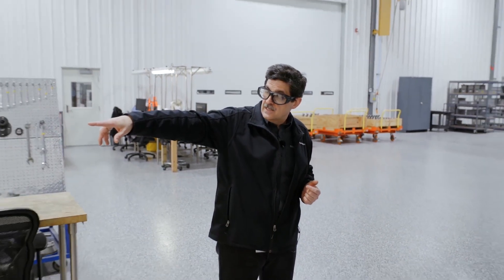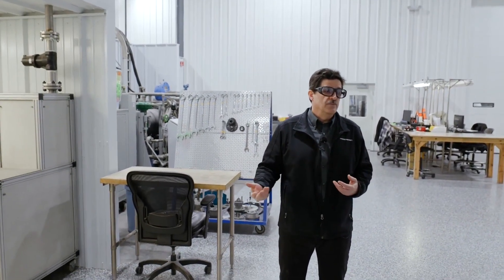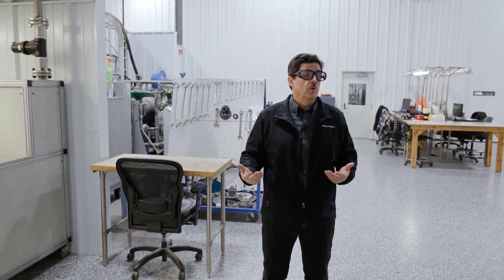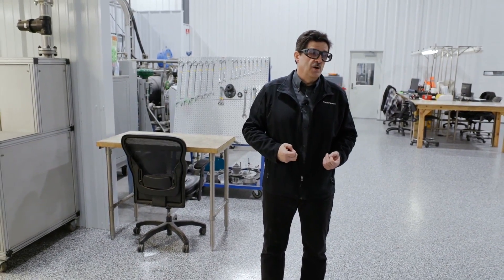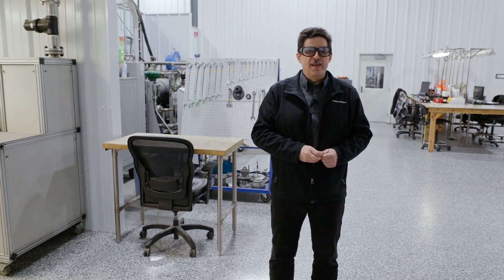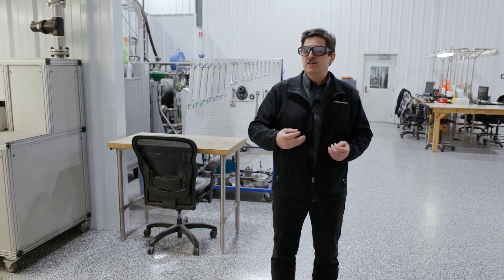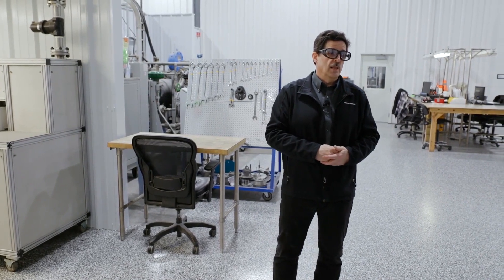You can see a dual fuel nozzle on the stand sitting right there. Although the industry standard for gas passage variation in a fuel nozzle is about four percent, we hold our fuel nozzle sets to two percent. That's part of being an independent — you have to push beyond what others in the industry do. That's a critical element to us.